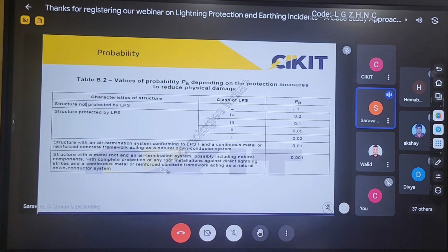If PB is 1, what will be the value of risk? If the risk is higher, then I will go for level 4 protection. In that case, the value of PB will be reduced to 0.2. So initially it was 1 and now it is reduced to 0.2. And if the value is still higher, I will go for level 1 protection, and the value reduces to 0.02. Since the value of PB is reducing, the corresponding risk component value also will be reducing. So this is how, by installing a lightning protection system, we reduce the value of risk due to lightning.